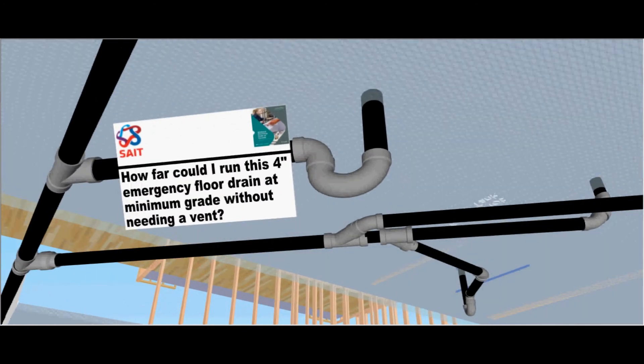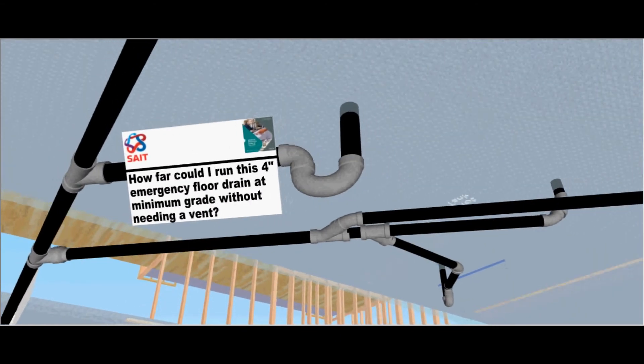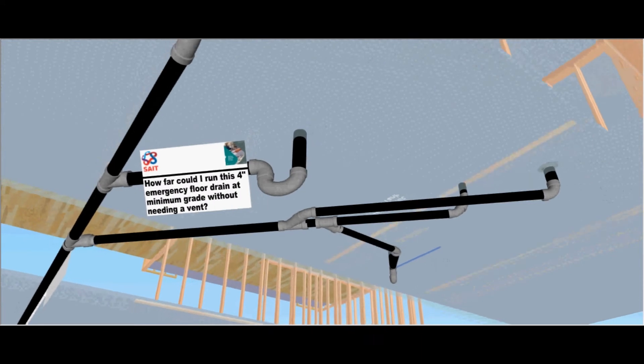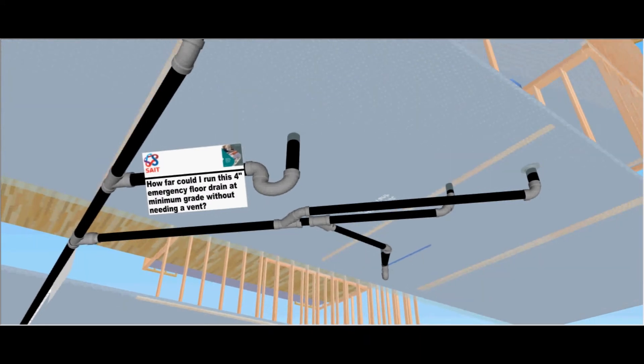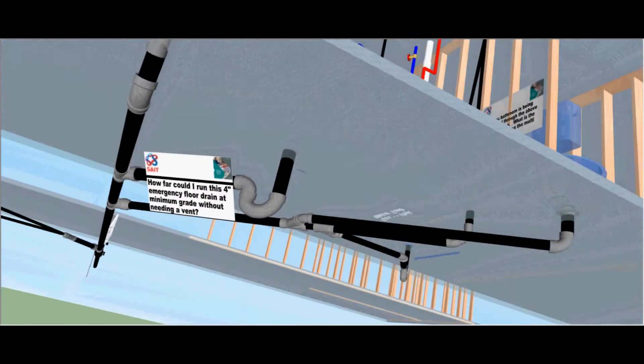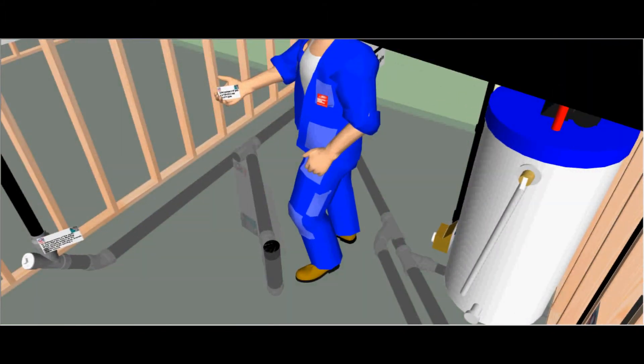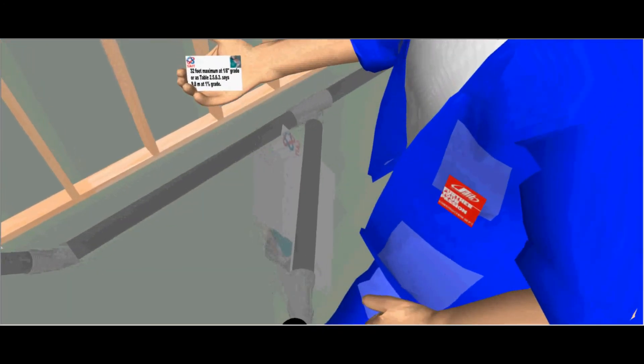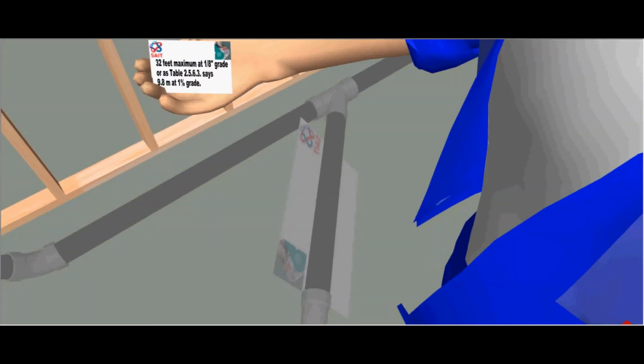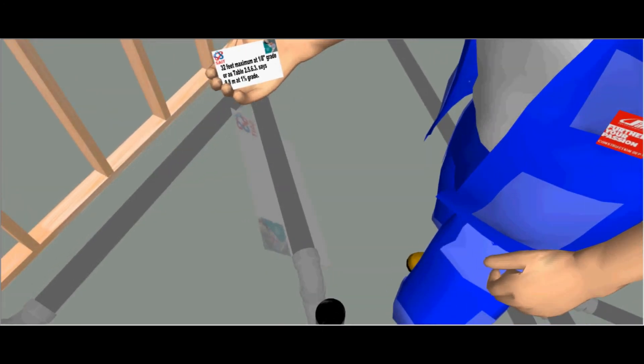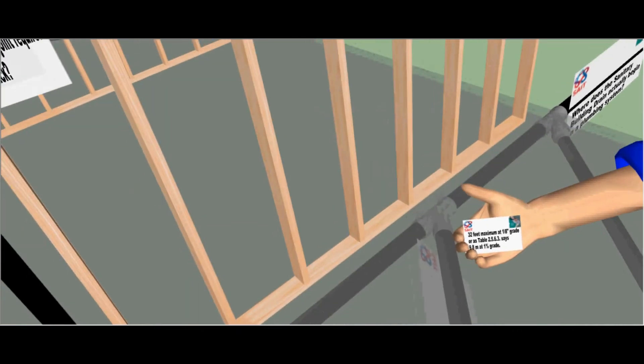So let's take a look. How far can I run this 4 inch emergency floor drain at minimum grade without needing a vent? Well, let's take a look. You could run this 4 inch floor drain at least 32 foot maximum at eighth of an inch per grade as it says on table 2563 or 9.8 meters at 1% grade.